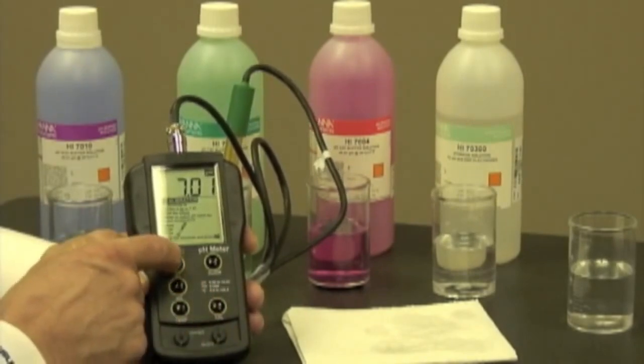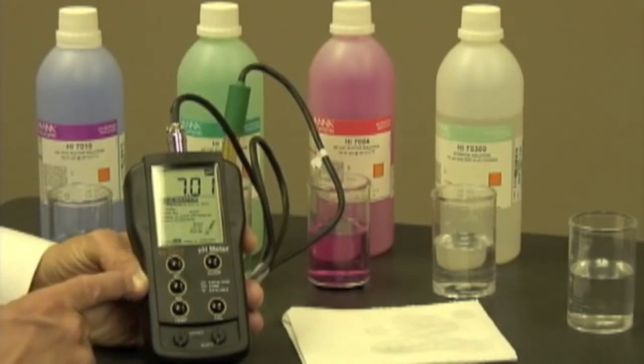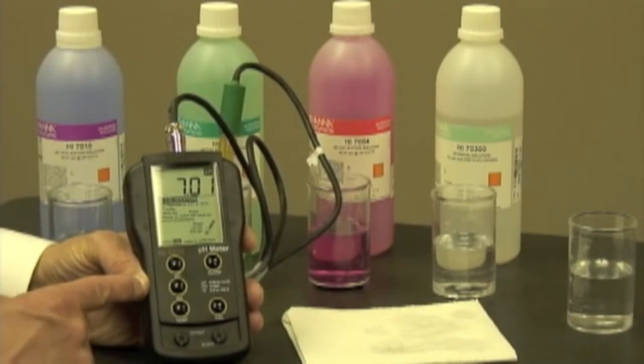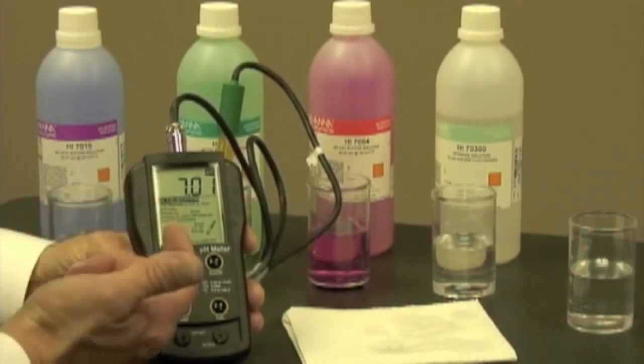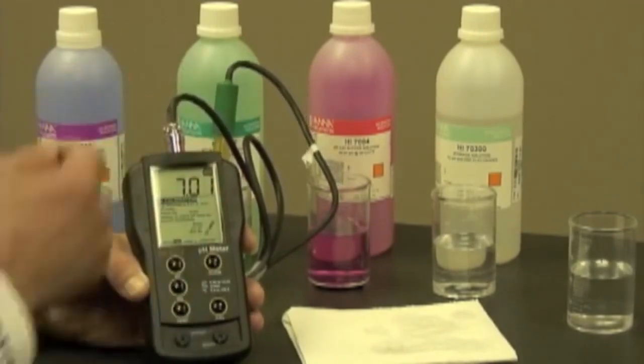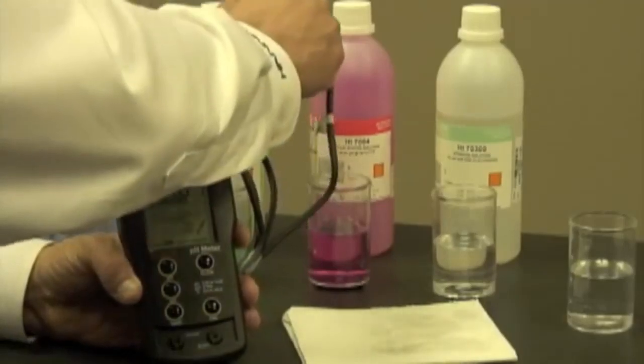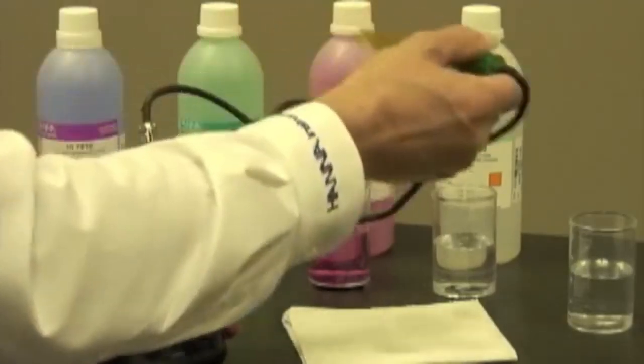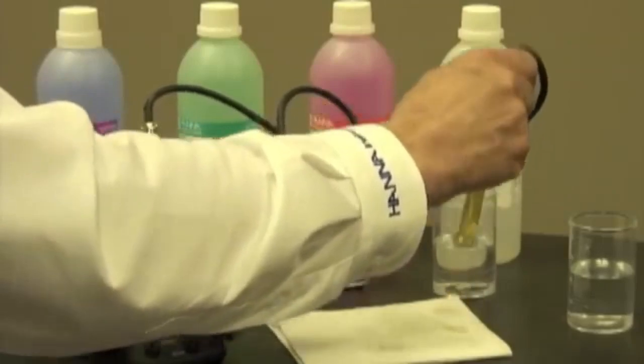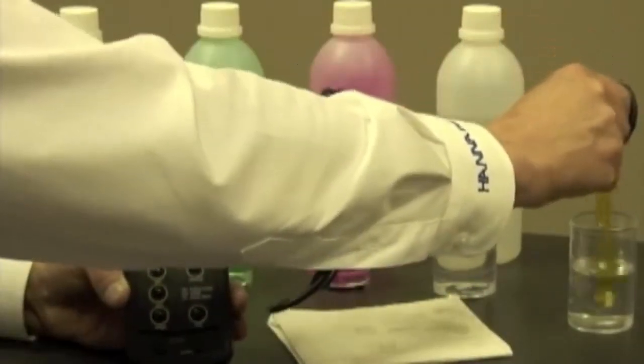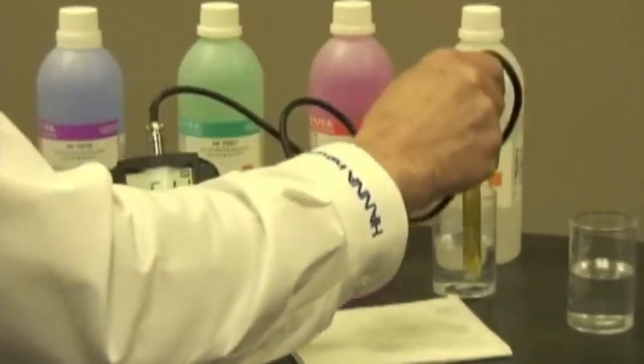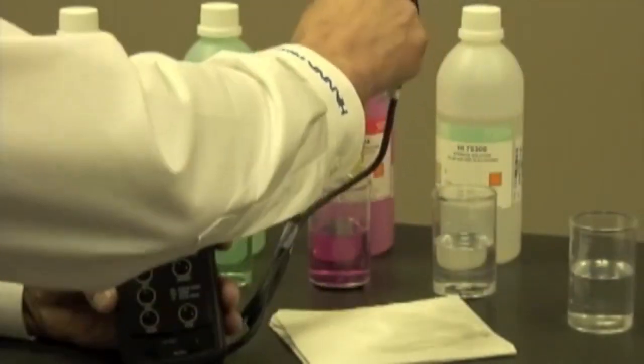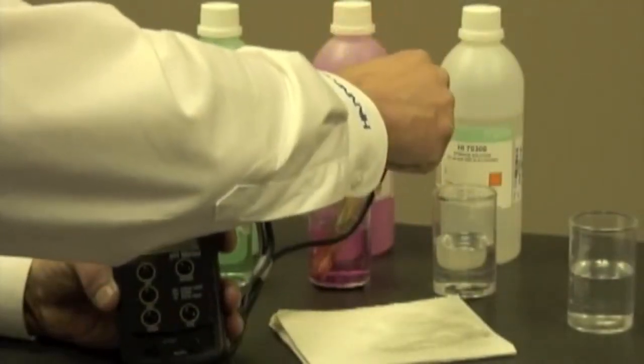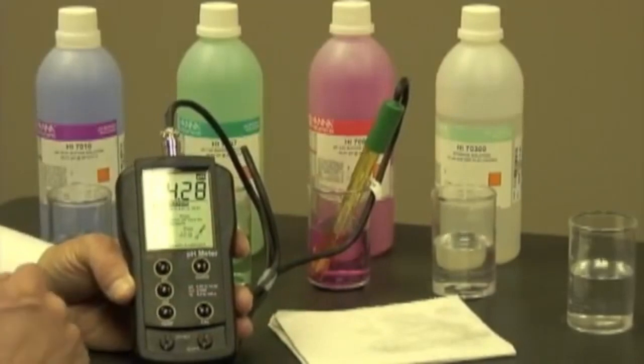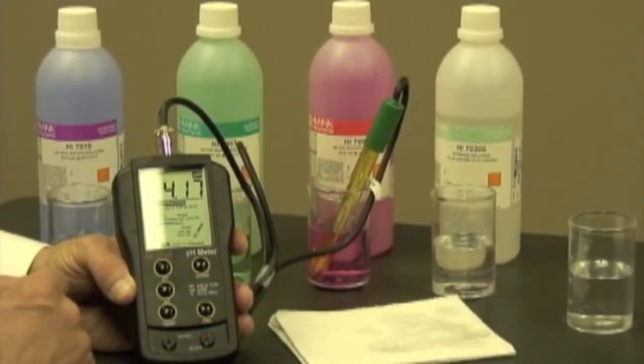I'm going to push the pH button. And depending on what I'm going to measure, if it's an acid or a base, I'm going to choose either a 4 or a 10. So in this case, since I'm going to measure something that's acidic, I still want to rinse my electrode off, dry it, and put it into a 4 buffer. Let it adjust.